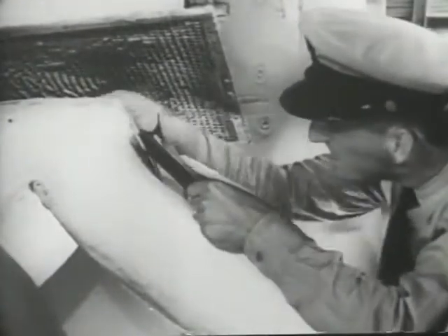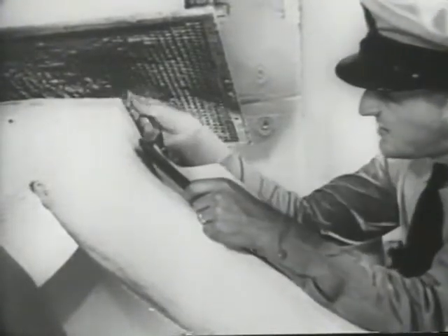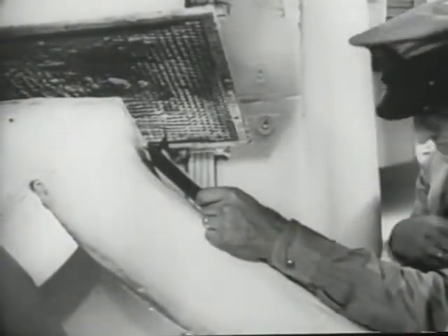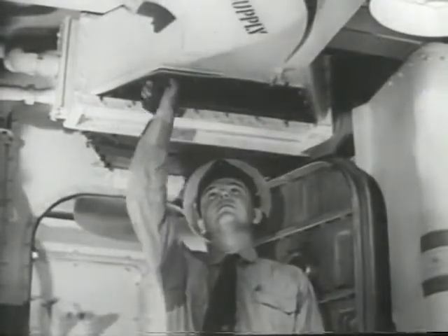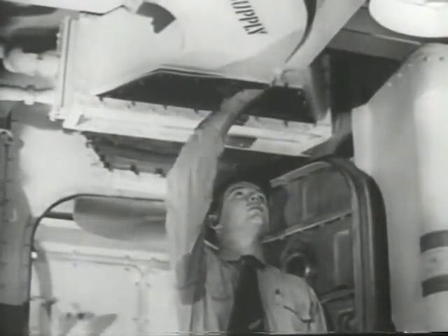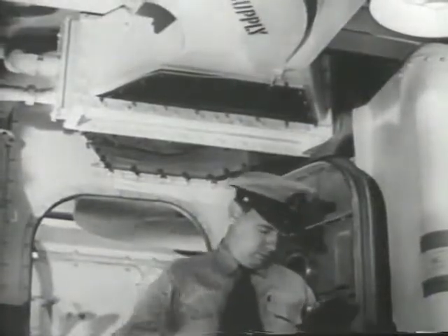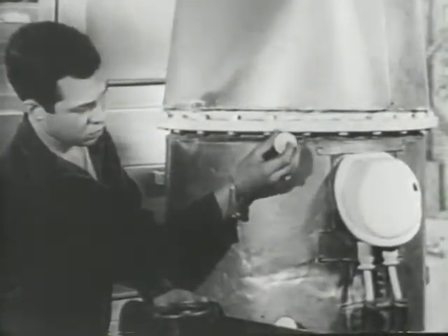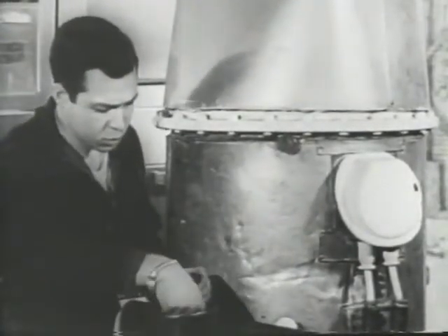Inspection requirements vary for different elements of the system. For example, laundry exhaust screens, where lint accumulation is a serious problem, should be inspected once a day. Heating and cooling coils should normally be inspected once a week. Other elements, such as ducts, where dirt accumulates more slowly, may require inspection only twice a year. Fans should also be lubricated on regular schedule.